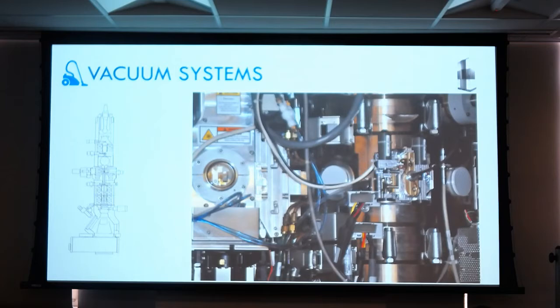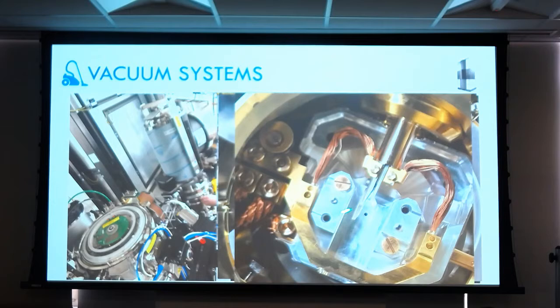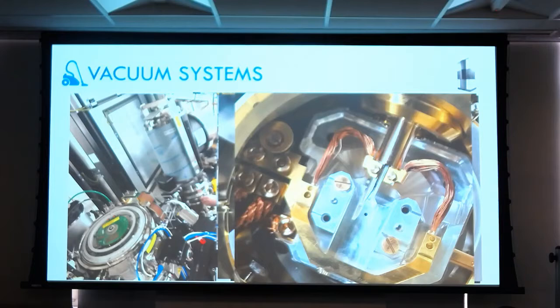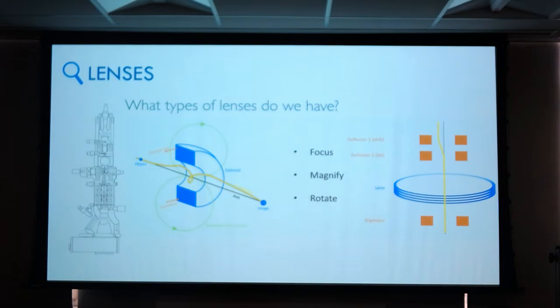Here's a picture of a Krios with an autoloader system. If you take the top off and this plate off and look in, this is actually where the sample is held. This is where the electron beam goes — so that big electron microscope, from here to here is not really the beam path. The column is like the graphite piece of a pencil — that's really all the space you need for an electron beam to travel through. Why all the shielding? Electron sources do kick out X-rays, there's quite a bit of energy, so there is lead shielding, and a lot of this is taken up by lenses and material to cool down the microscope.